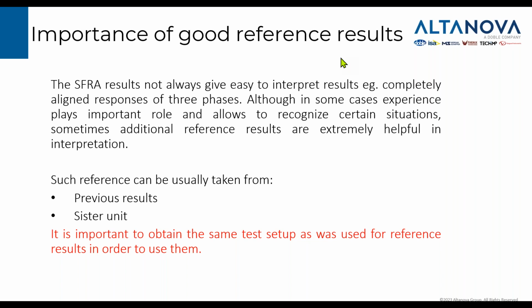Before, we analyzed our traces on the basis of comparison between phases. Unfortunately, this is not always the best way, because our traces can differ significantly without the transformer being damaged. So there are two other options. We can compare our traces with previous results, ideally made on the same transformer, ideally in the same location and the same condition. For that, we need to know how it was tested before and what influencing factors could have affected these traces, so that we can follow the same strategy.